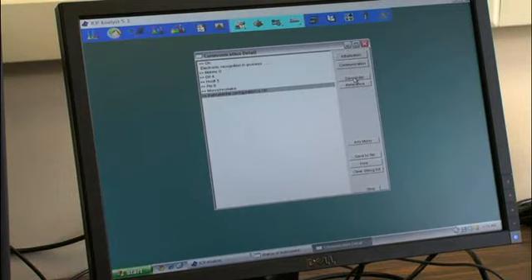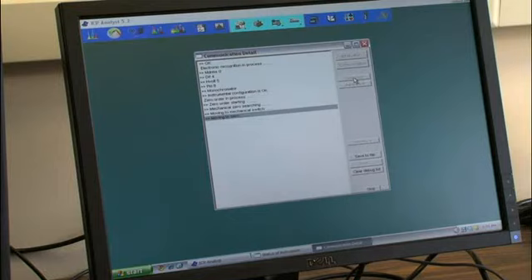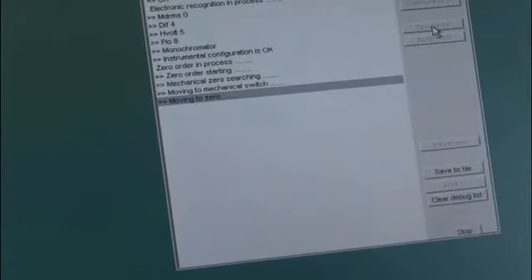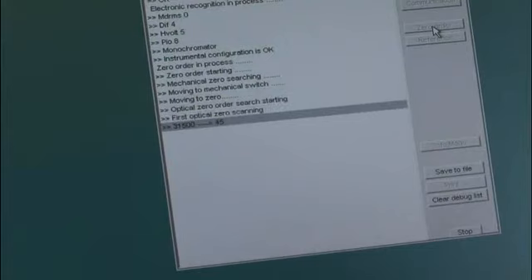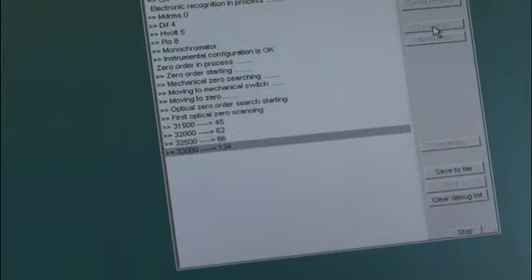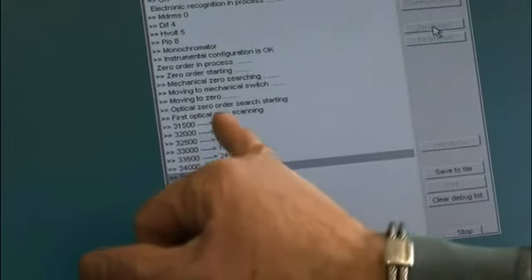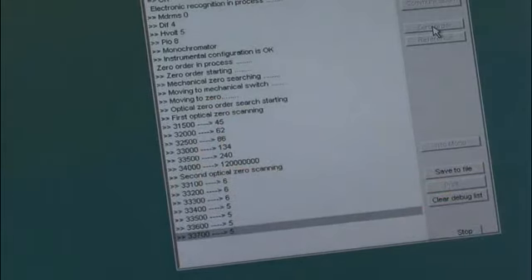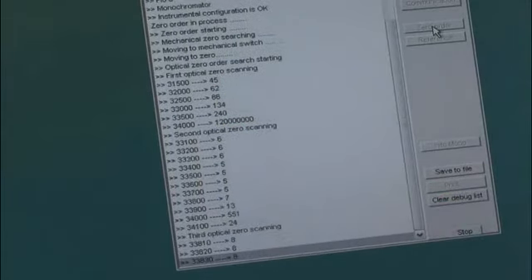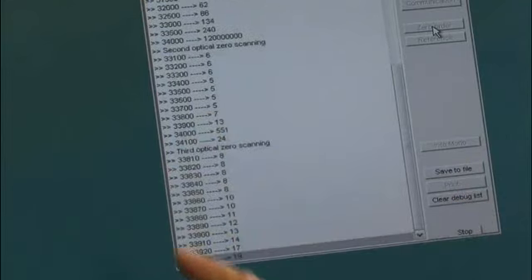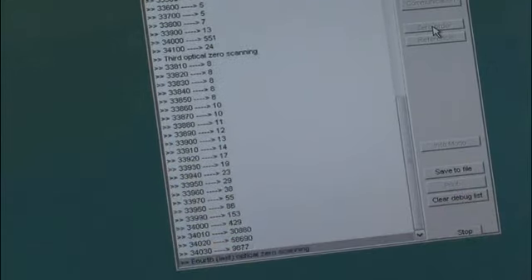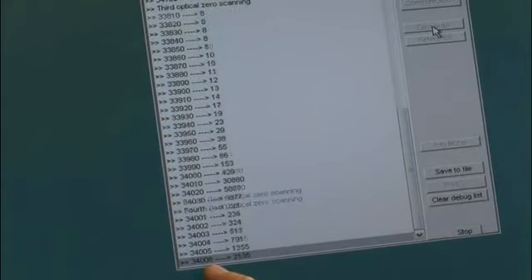The first scan will be in steps of 500 motor steps. The second one will be in 100, then 10, then 1. So it gets more precise, and as it gets more precise, the voltage is cut down for each scan because otherwise it'll overrange. So this only needs to be done if the power has been off, if you've lost communication, or if you've lost the reference. So it's going to begin at, these are motor steps, these are intensities, and you'll see that the first scan overranged. The most important is you don't want the last scan to overrange because this is 500, this is 10. Oh, third is 10, yeah, and the fourth is in one-step increments.